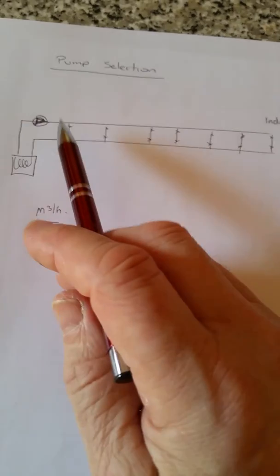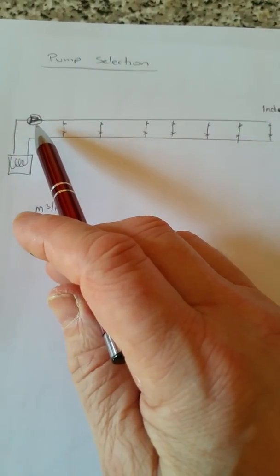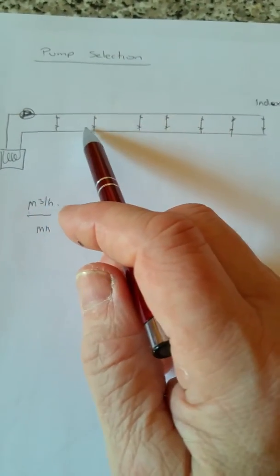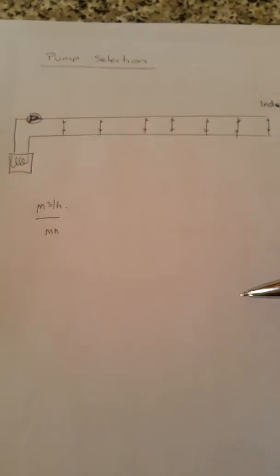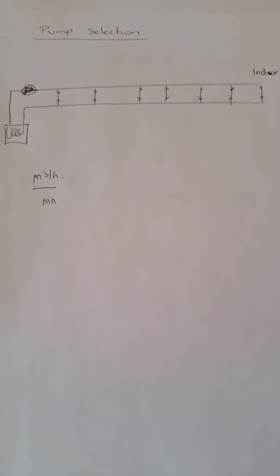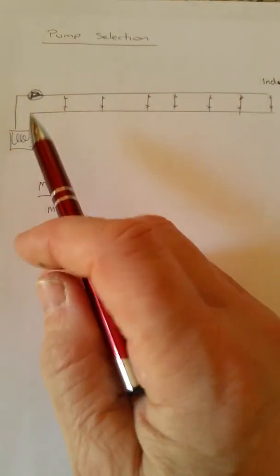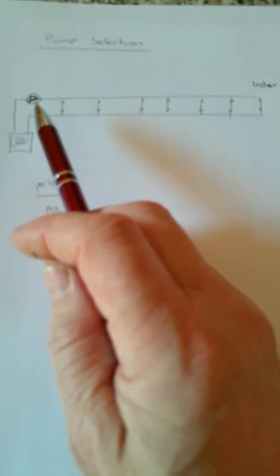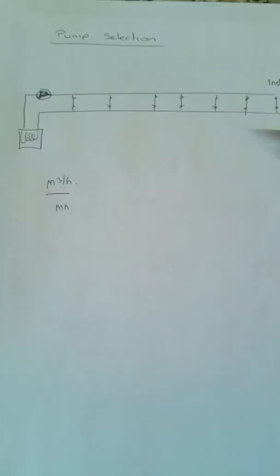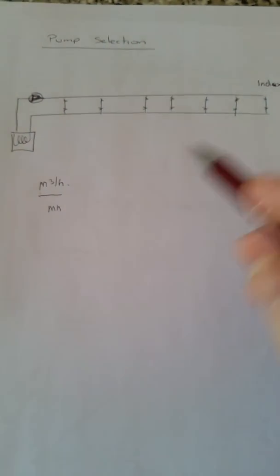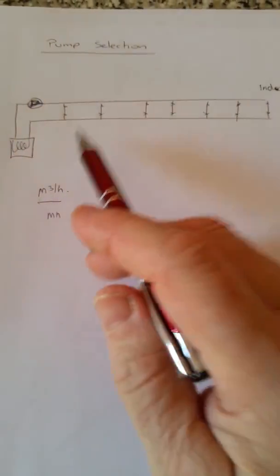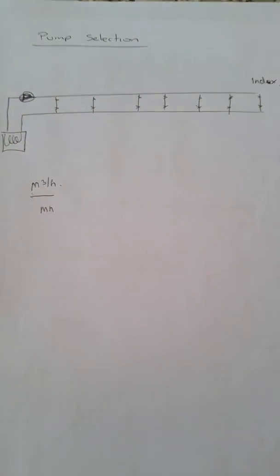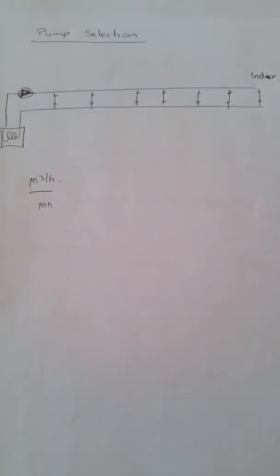And that's simply because all you've got is a reduced flow, and by balancing in that way, all you're actually doing is sharing the reduced flow across those radiators. You're not actually getting a proper flow rate through each one. So it would be very, very important to know that you actually had adequate flow available from the pump, or excess flow available from the pump at a pressure above the resistance calculated for the whole system before you started balancing down.